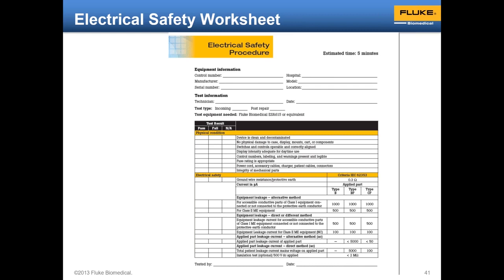If you have this already in some other automated workflow in your computerized maintenance management system, that's fine. But you have to have some place to report your results, and this is what we're showing you here. Okay, who tested it? What date was the testing done? And some information about what exactly is the patient monitor that we tested, including its serial number and its hospital inventory control number. Okay, so these are the tests that would need to be included, and they come directly from the IEC 62353 direct method test procedure.